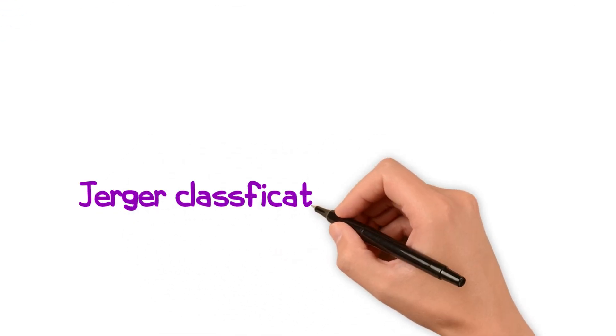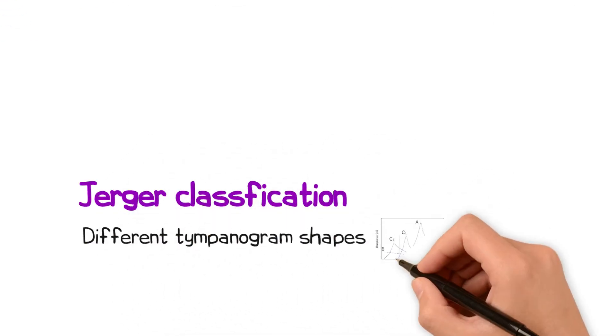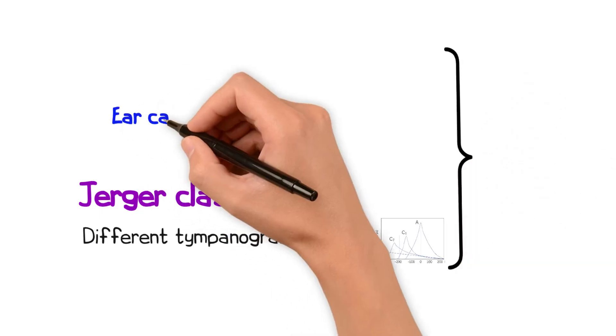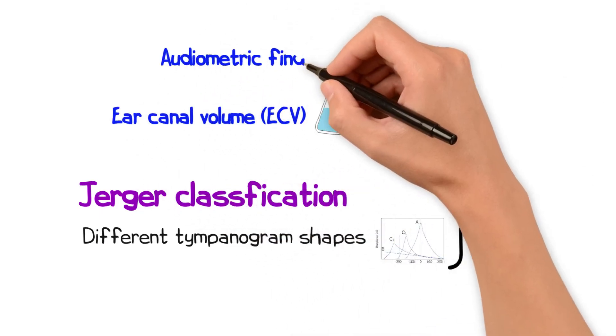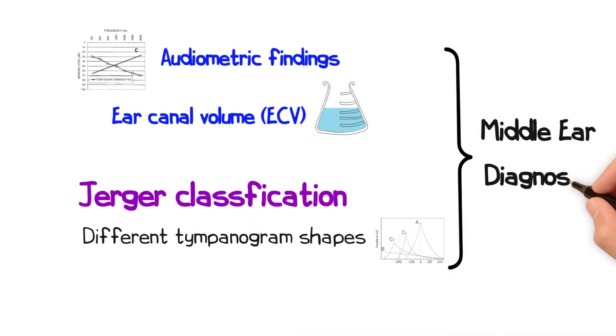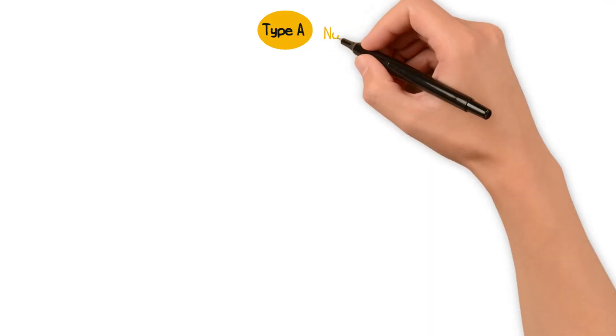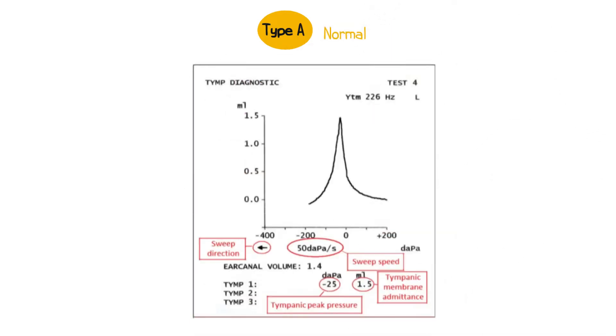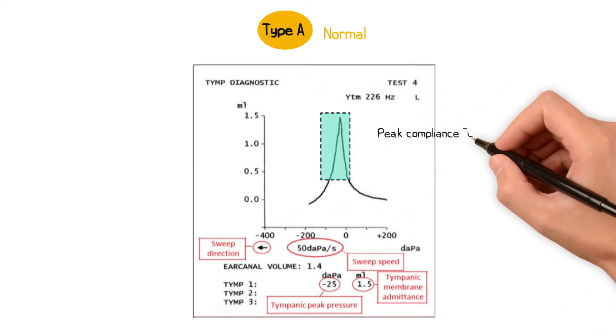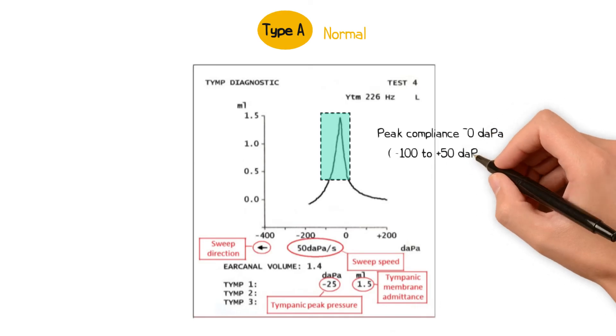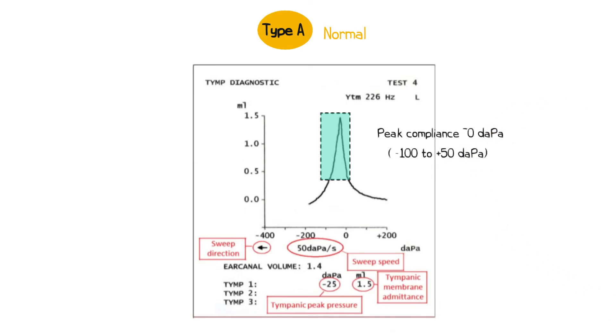The Jerger classification describes different shapes of tympanograms which, together with the ear canal volume and audiometric findings, can help diagnose middle ear pathology. Traces can be classified as type A, B, or C, each with their own subtypes. A type A trace is a normal result where the peak compliance occurs at 0 decapascals, which is atmospheric pressure, with a sharp decrease on either side, indicating normal middle ear pressure and mobility of the tympanic membrane.